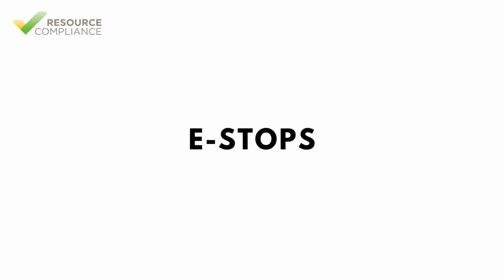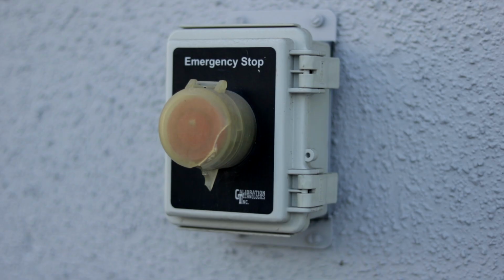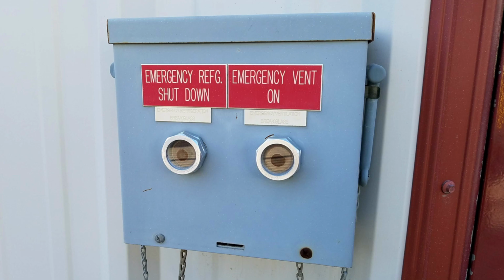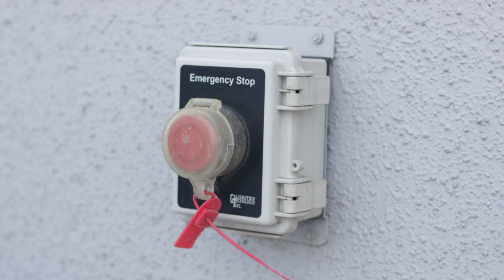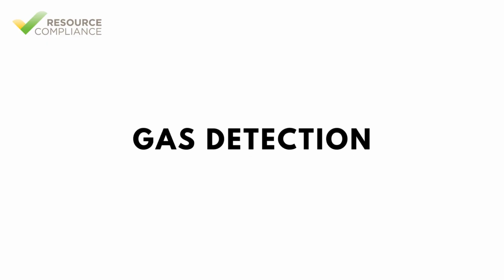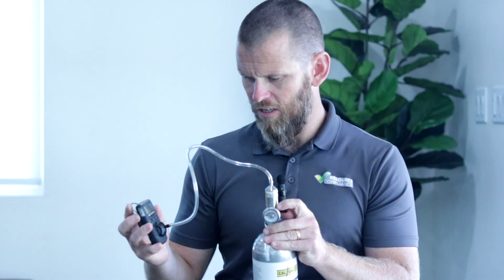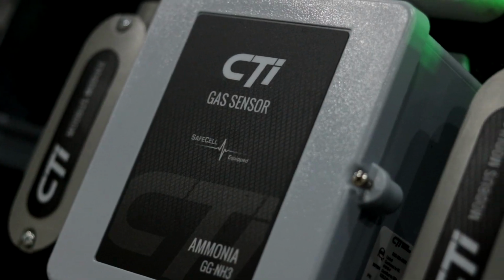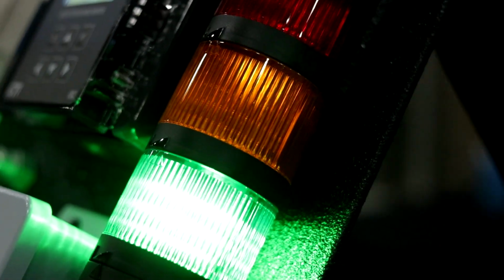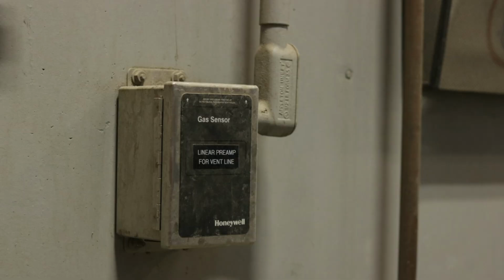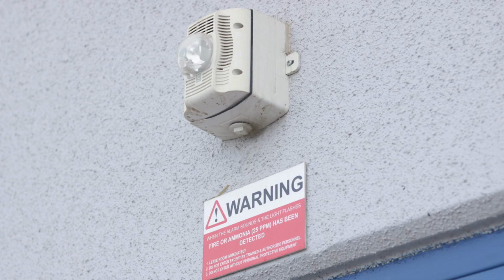Emergency stop switches, or e-stops, must be inspected every 6 months to verify that the switch is in good condition and properly labeled. Annually, the switch must be functionally tested to confirm all associated equipment is de-energized when the switch is activated. Most gas detection manufacturers recommend that gas detectors be calibrated every 6 months. In addition to calibration, the detectors should be functionally tested annually to verify that the interlocks and alarms are functioning as designed. During each calibration, the detectors and alarms should be inspected to verify that signage is installed and detector enclosures are in good condition.